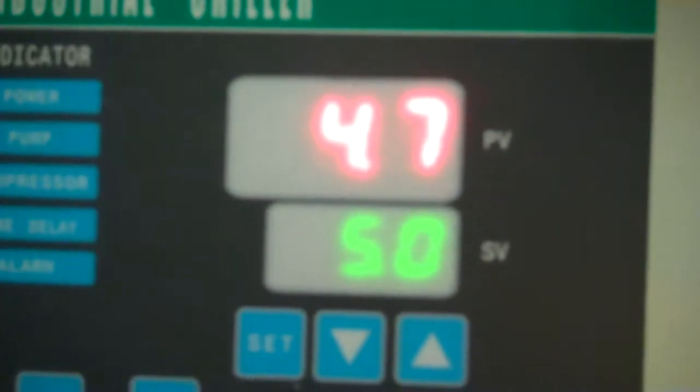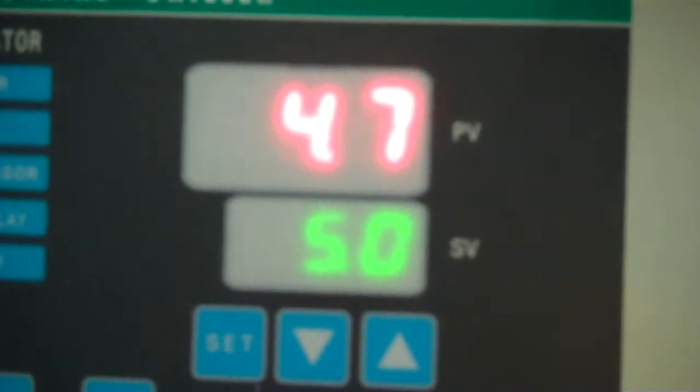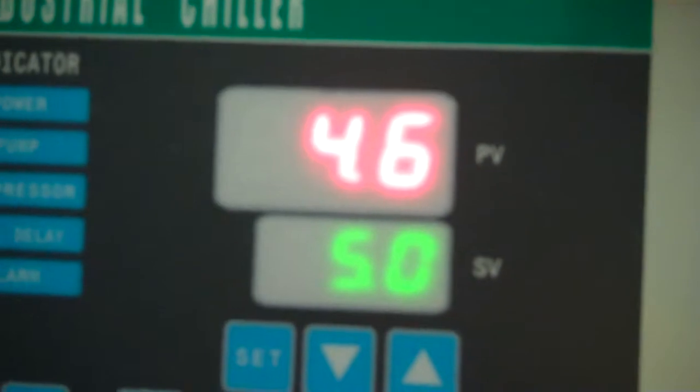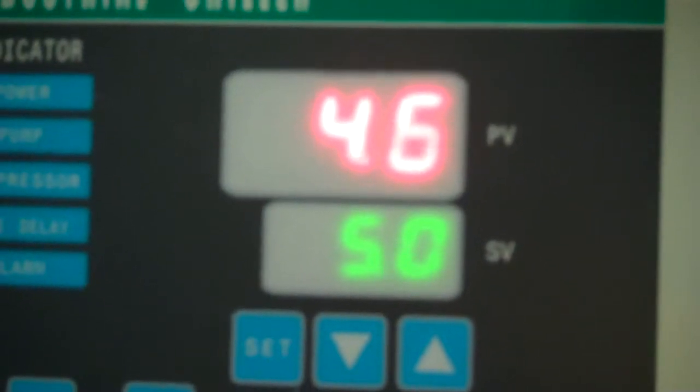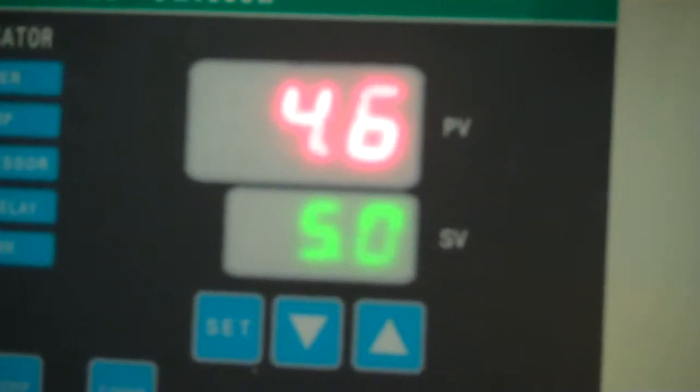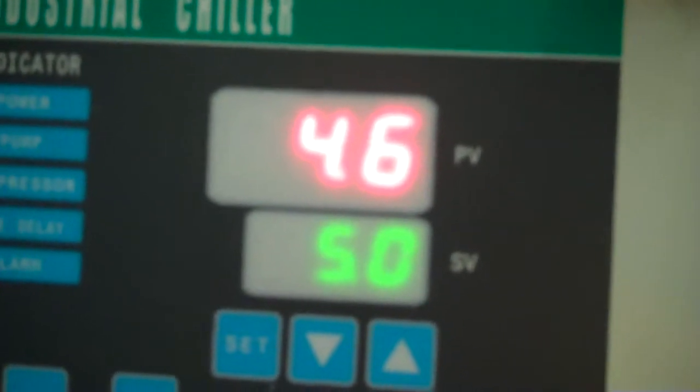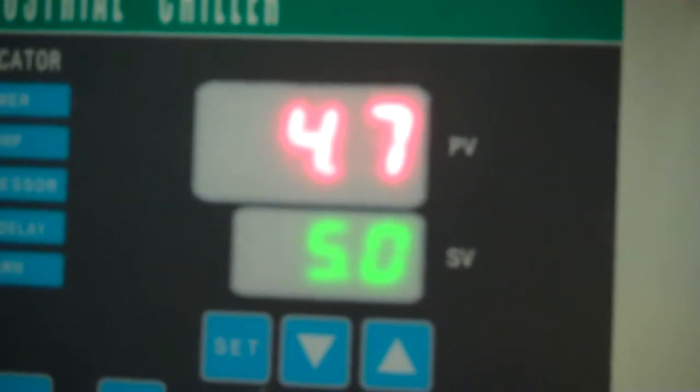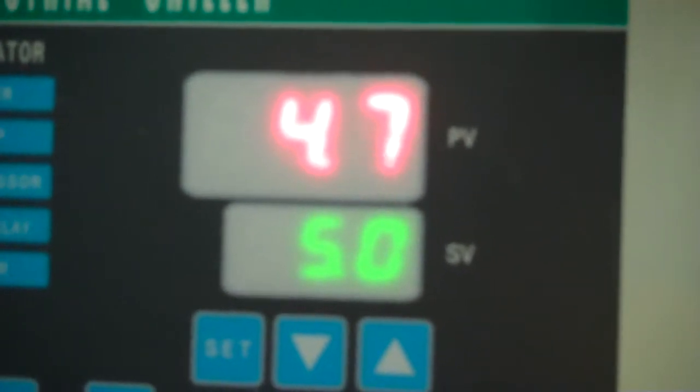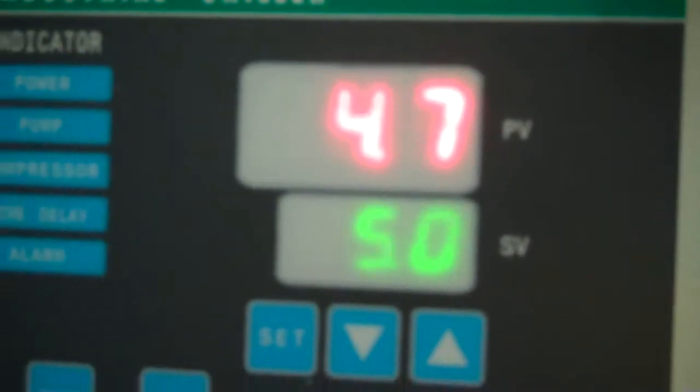What takes precedence over that is our set point. Our process temperature needs to get up a little bit higher before it's going to allow the system to turn back on again. In this case that's six degrees centigrade before this system will turn back on.